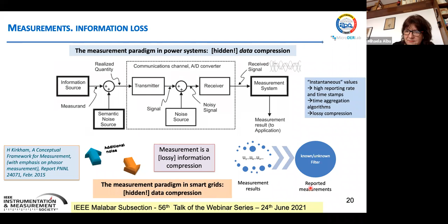So you might ask yourself, because this aggregation is very simple. If we think of power quality, the RMS voltage that is reported, at first glance, is the squared average of 10 individual voltage RMS values over 200 milliseconds. Then the second reporting is over 3 seconds, and then about 10 minutes, and then 2 hours. So this averaging is something very simple, but it's a low pass filtering. And you might ask yourself, why? If we know that this introduces so much additional uncertainty, why shall we use it?